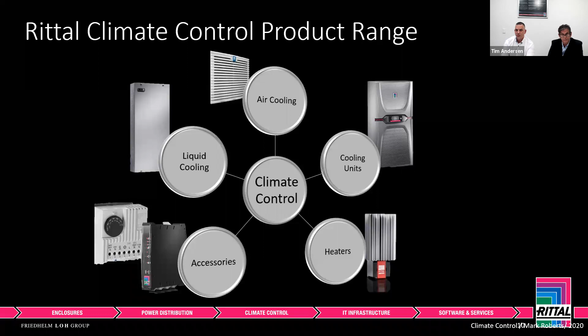So this brings us to a point where we have compiled all this information ready to be used in a practical solution. So far, we've considered the importance of thermal management, looked at the heat load and what causes them, what drives the temperature up in an enclosure. We have considered our internal temperature. This will be our limit set that we want the temperature to get to within the enclosure. And then we've looked at means of dissipating it. Some of it will occur naturally through the enclosure material, and the balance of it will need to be dealt with by an appropriate product that is sized according to the design and environment. So putting this all together is made easy with Rittal's latest tool, Rittal Therm 6.6.